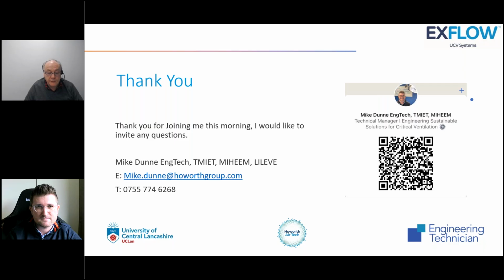Thank you. Another attendee has asked if you could talk us through concisely some of the key parameters for UCV testing. Yeah, so the testing of a UCV is laid out in chapter 12, and the three tests are integrity testing of the filters, the downflow grid testing, and the non-entrainment test, and they must be done in that sequence. You can't jump one in front of the other.